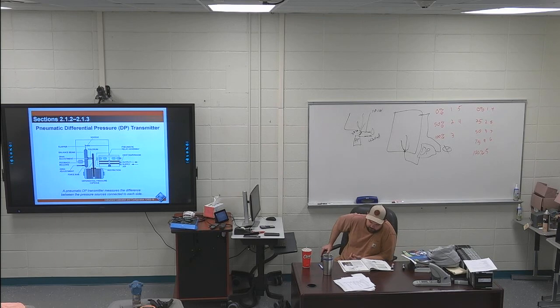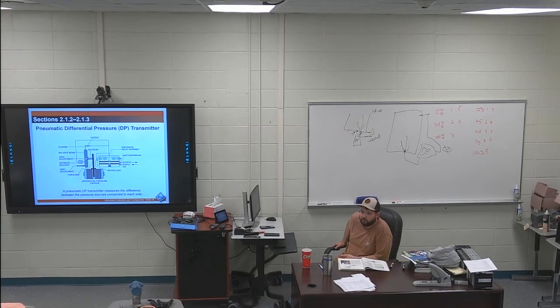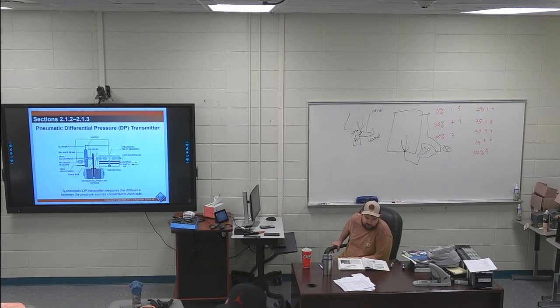Page 11. This just talks about other calibration points, which is just the math. I have the first paragraph on page 11 highlighted. For other calibration points, determine the actual range of the span and figure the differential pressure at each of those points. The range of the span for 5 to 50 inches of water is 45 inches of water. 5 minus 50 is 45. For the 20 to 255, I'm not going to do all that, but you're just finding the span. You're just subtracting the range. Got to know how to do that.